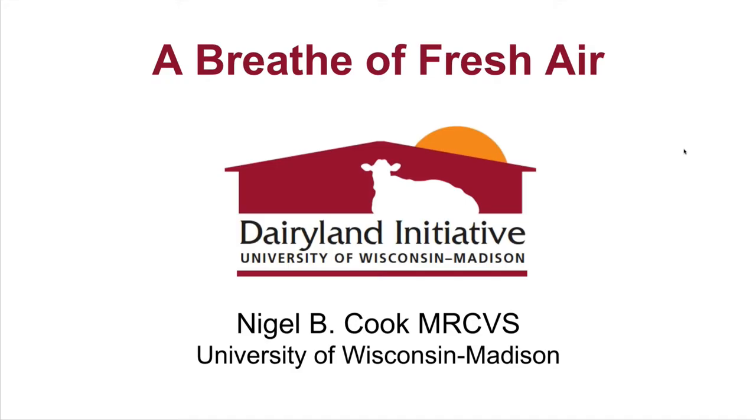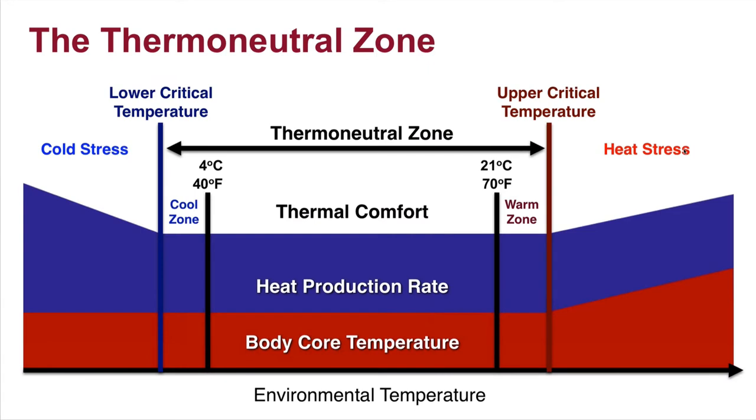Well, thank you. We're going to talk about a little bit of ventilation for cow barns, and with 75 slides I've got a bet with Mike that I can get through this in 45 minutes, so hold on tight. This is the thermoneutral zone figure for adult and young calves. Generally, cows do quite well within a range of temperatures between 40 and 70 degrees Fahrenheit. They're quite remarkably cold tolerant, but on the top end our cows become heat stressed quite a ways before humans are bothered by heat.